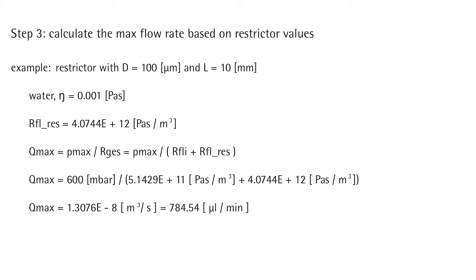The fluidic resistance of the restrictor is dependent on the power of 4 of its diameter, but only linearly to the length. The diameter is the most significant parameter to choose. With the internal resistance of the pump, the viscosity of the liquid, and the dimensions of the restrictor, it is possible to find the resulting maximum flow rate.